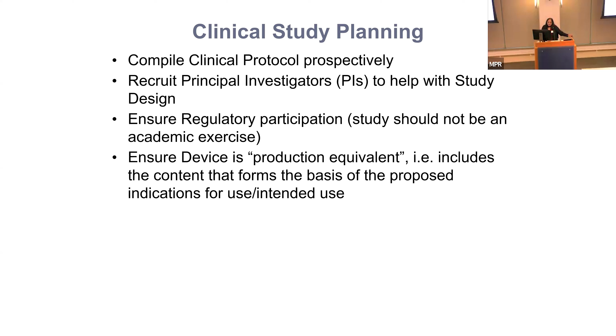Don't overreach. Make sure there are principal investigators to help with study design and regulatory input, and make sure that the device that you're testing in the pivotal is a production equivalent. That means it needs to have all the software modules. If you have CBT in there and your commercial product is supposed to have 4 modules, don't do the study with just 3, because the 3-module one is what you're going to get clearance for. Okay.